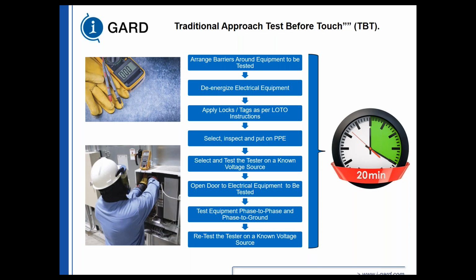Select the appropriate tester and test the appropriate tester. Now we open the door. Test phase to phase and phase to ground, retest the tester on a known source. Now we've established an electrical work area.